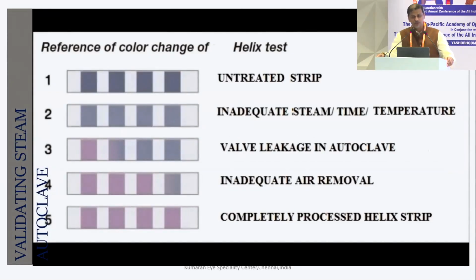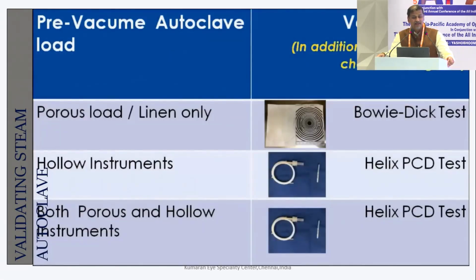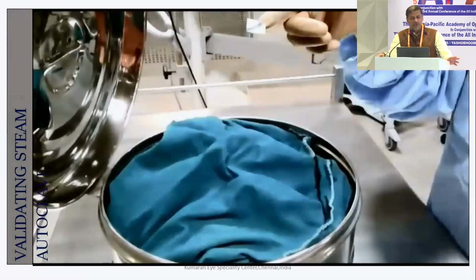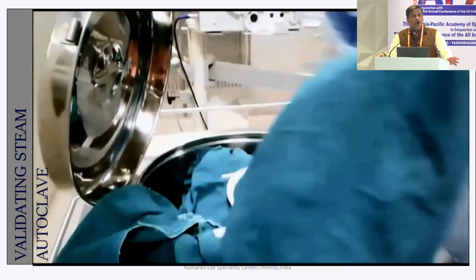Use a troubleshooting device or a strip or a thing that you can stick in your CSSD area and teach the staff how to troubleshoot a failed PCD test. So pre-vacuum autoclave, porous load: use the Bowie-Dick test; hollow instrument: use the PCD.